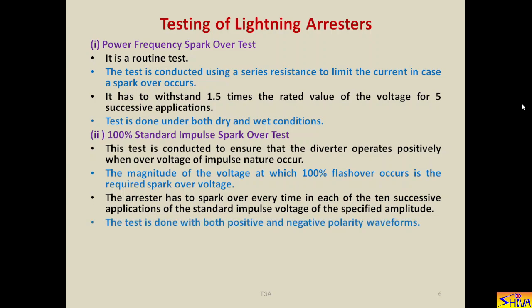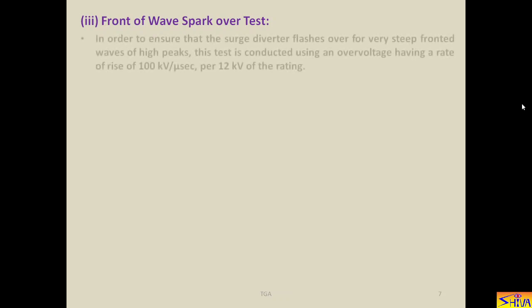The test is done with both positive and negative polarity waveform, because in actual system the impulse can be of positive polarity as well as negative polarity. So with both these polarities, the lightning arrestor must spark over at the specified magnitude. So we are performing this test so that equipment is protected. Next is front of wave spark over test.